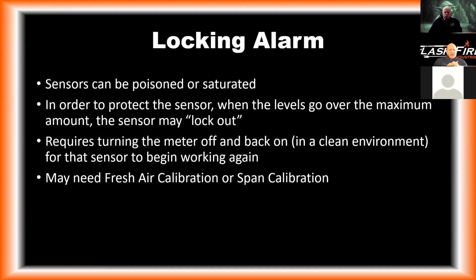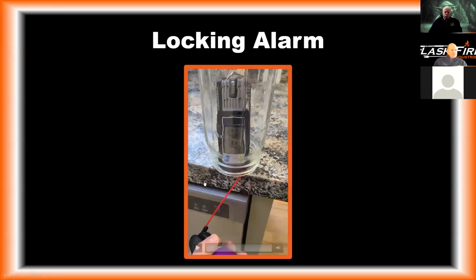And then second is what I'll see a lot of times: when we have a faulty boiler, we'll be metering in and around it. And maybe someone will put the meter down to check something with the boiler, and they'll put it right where the exhaust is. And so the exhaust goes right into the meter and actually saturates it. So just be aware of those things. And it may need a fresh air cal or a span calibration after it is restarted.